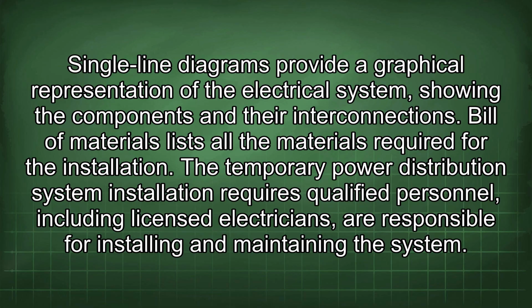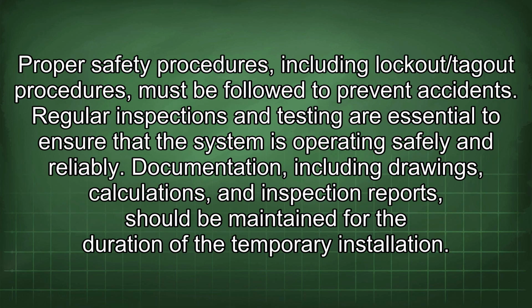The temporary power distribution system installation requires qualified personnel, including licensed electricians, who are responsible for installing and maintaining the system. Proper safety procedures, including lockout/tagout procedures, must be followed to prevent accidents. Regular inspections and testing are essential to ensure that the system is operating safely and reliably. Documentation, including drawings, calculations, and inspection reports, should be maintained for the duration of the temporary installation.